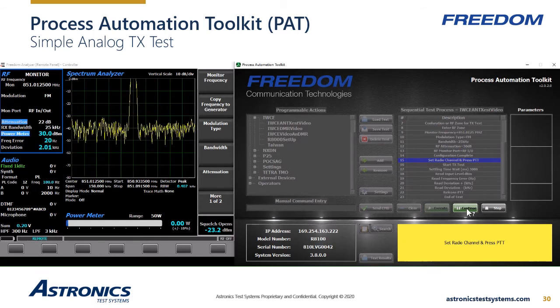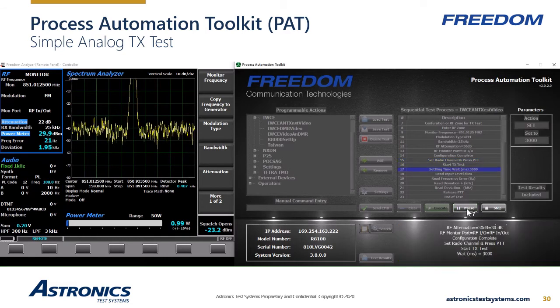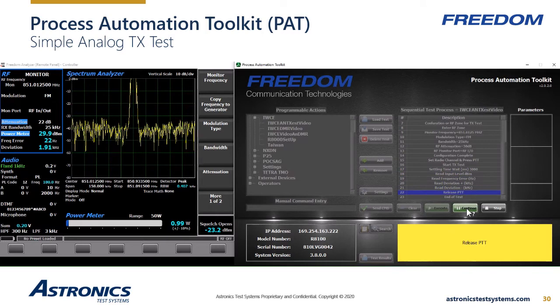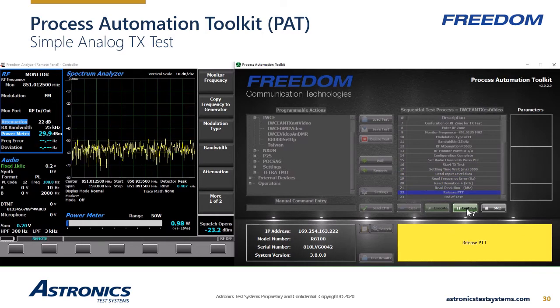Press the PTT on the radio and we can hear the 1 kHz tone coming through the speaker of the radio. Press continue. 3 seconds wait time. It made some measurements. Release PTT. Press continue.